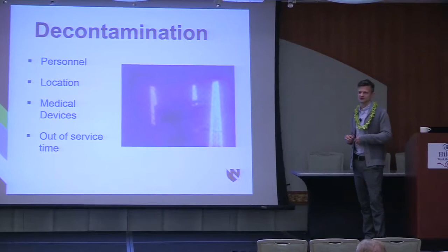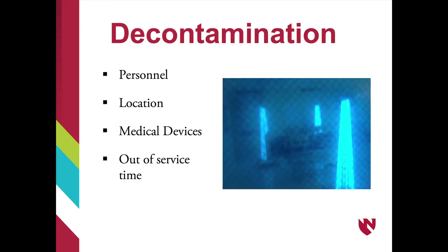We found out that there was a sleeve system that the manufacturer made for that particular device, and we used that, and that helped us reduce, one, the potential for any contamination on the device. Once we took off those sleeves, we had pretty solid assurance that any contamination went with the sleeve. This was also something that wasn't coming into contact with the patient. And then that helped us reduce our burden of cleaning from 3 cleans down to 1, okay? So again, it's looking at that triangle and implementing different levels of controls. And then also consider time out of service. We had the ability to take this unit down for a week.